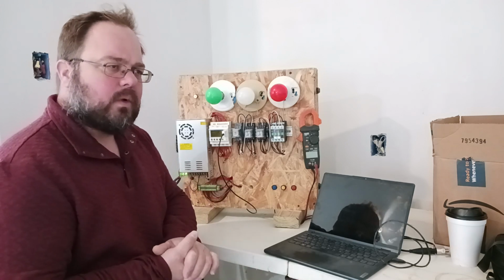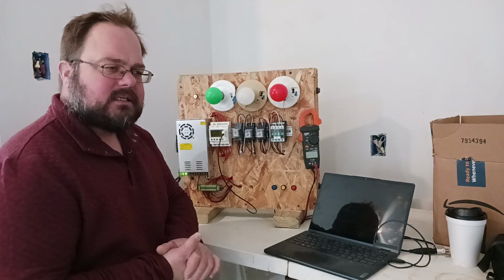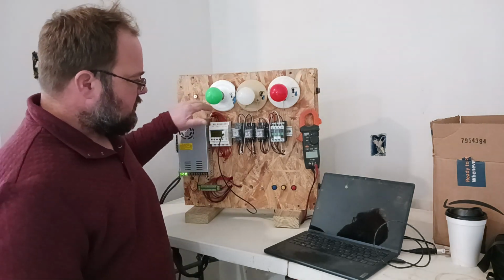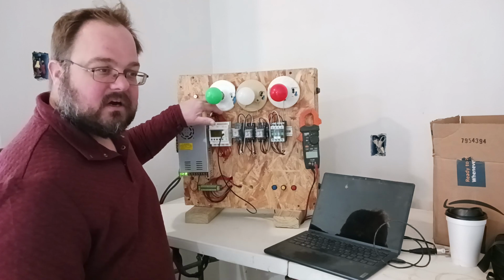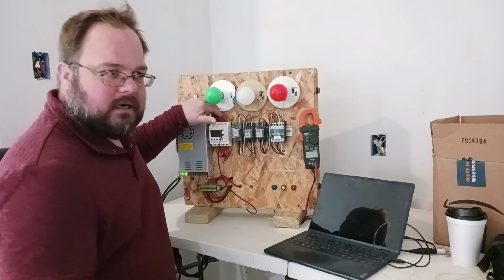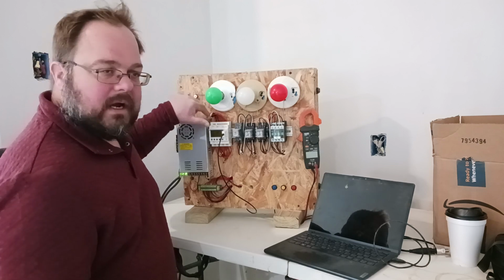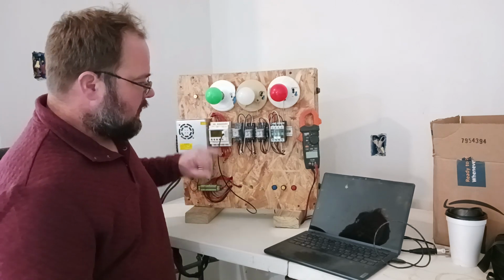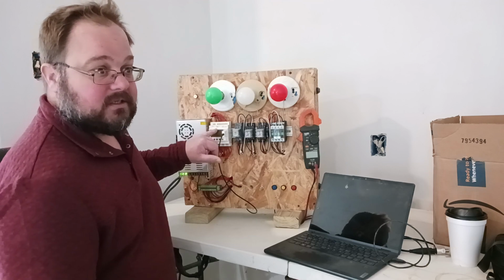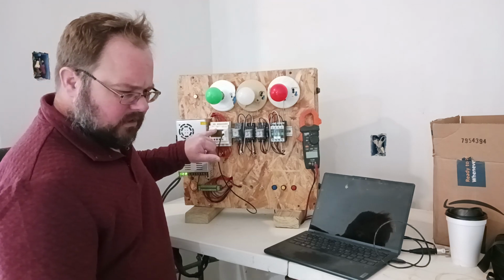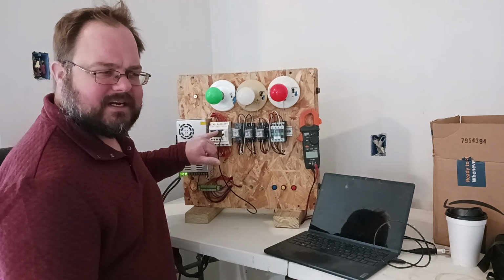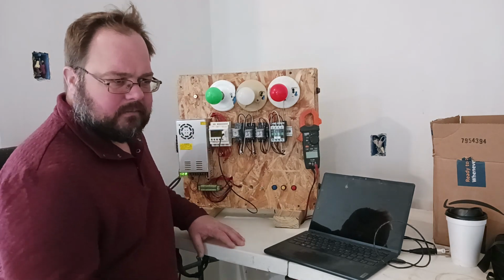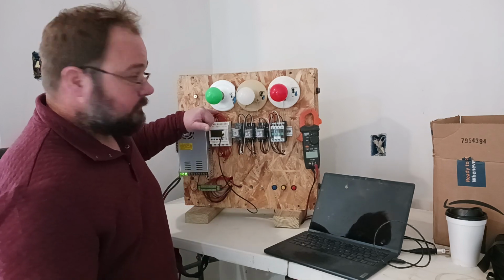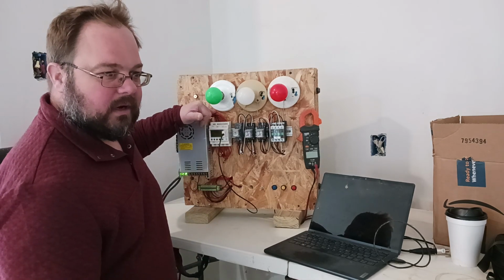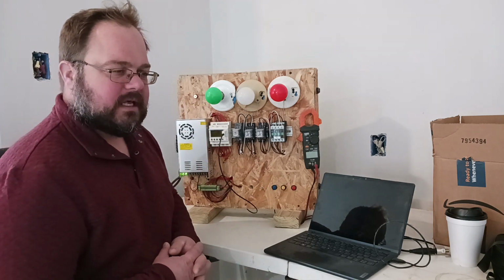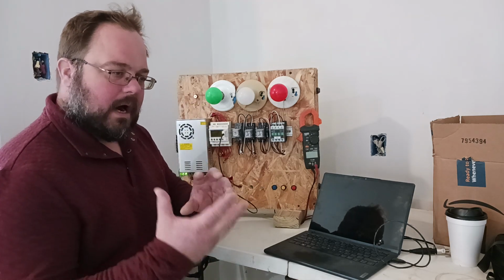What that means is, are we hooking up the negative side of the DC circuit, or sending our signal as a negative or positive? Is our signal on the positive side of the DC circuit or the negative side? These are all red, all positive, because this Zelio Logic PLC requires that, so I didn't want to do something the manufacturer doesn't recommend - I just did my positives like the manual says. Sometimes you're just stuck needing to do it one way or another, but there are some PLCs that have a common, and you can wire them either way.